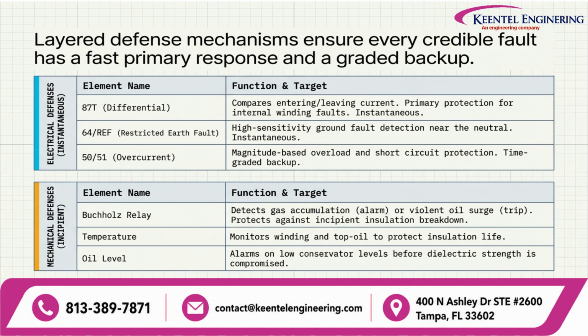The primary protection is typically transformer differential protection, commonly identified as the 87T element. The 87T function compares the current entering and leaving the transformer protection zone. Under normal operating conditions, these currents should balance after accounting for the transformer ratio and phase relationships. An internal transformer fault disrupts that balance, producing differential current and allowing the relay to trip rapidly. The next layer is restricted earth fault, or REF, represented here by the 64 or REF function. REF provides highly sensitive ground fault detection, particularly for faults near the transformer neutral. Then we have 50 and 51 overcurrent protection. These functions provide magnitude-based short circuit and overload protection and can serve as time-graded backup.